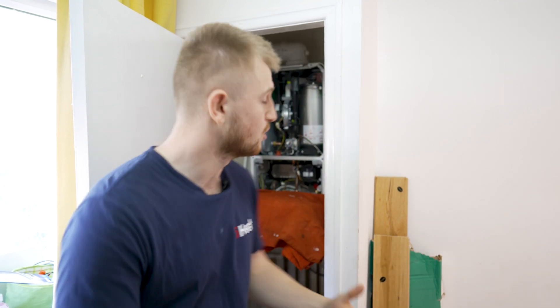Welcome back to the iHeat YouTube channel. Today we're doing a day in the life — a servicing episode where we're going to three different houses doing three different properties and servicing the boilers. Simon is currently downstairs cleaning out the condensate trap of this Worcester 4000 which was installed a year ago by iHeat. For servicing we're going to be doing a flue analysing test, a fan pressure test, a gas rate, and also checking the general installation to make sure it's all up to scratch with gas safety regulations and manufacturer specifications.